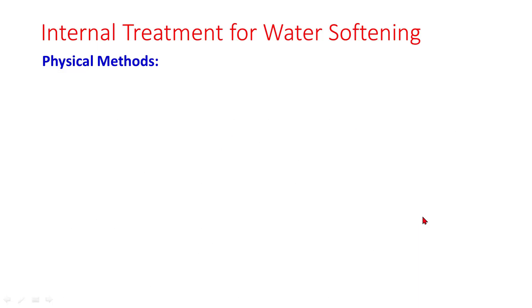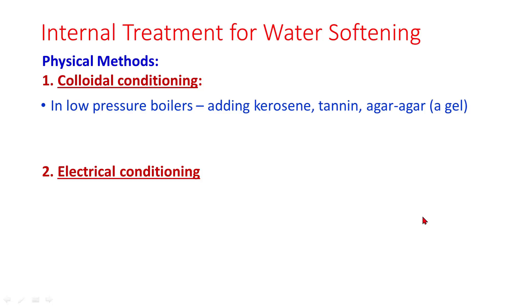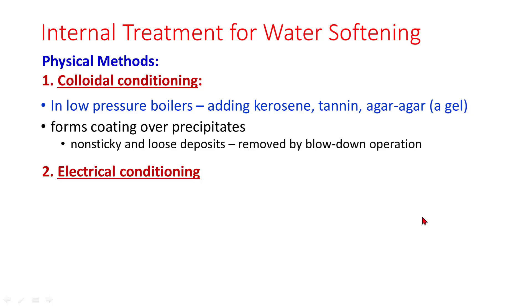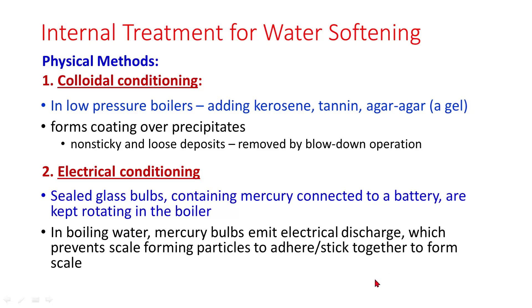Physical methods include colloidal conditioning and electrical conditioning. In colloidal conditioning for low pressure boilers, kerosene, tannin, or agar agar is added. These substances form a coating over the precipitates, resulting in non-sticky and loose deposits that can be removed by blowdown operation. In electrical conditioning, sealed glass bulbs containing mercury connected to a battery are kept rotating in the boiler. The mercury bulbs emit an electrical discharge, which prevents scale-forming particles from adhering together to form scale.